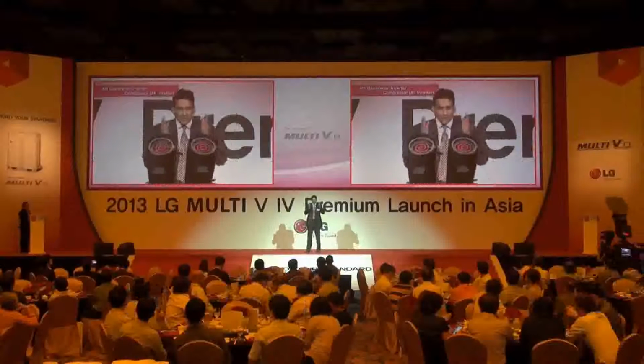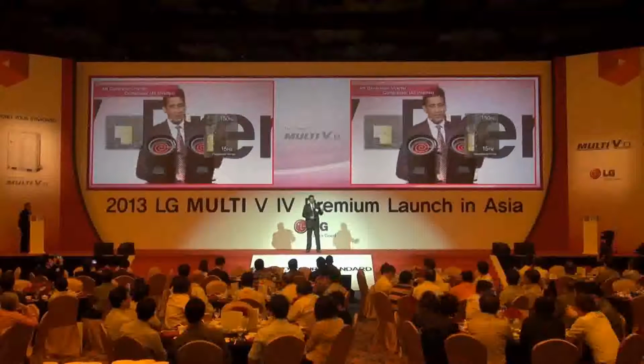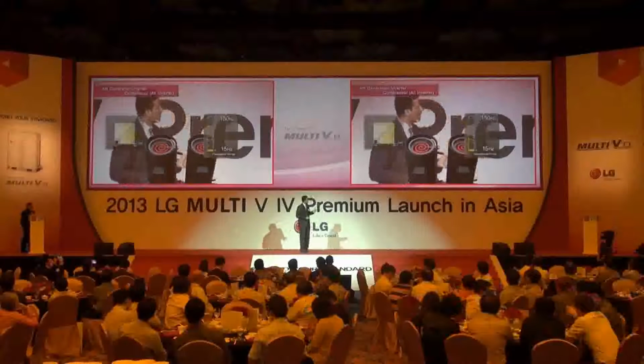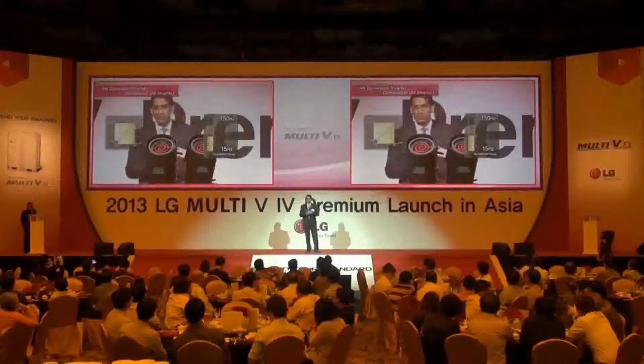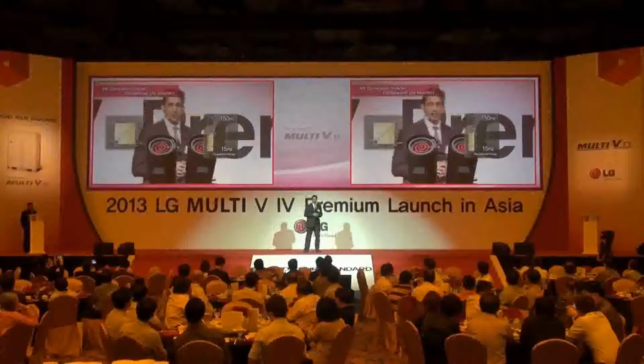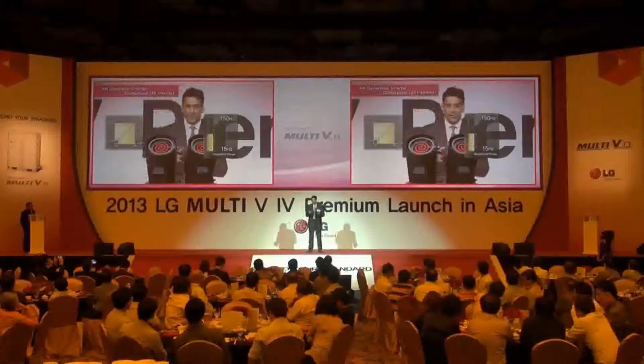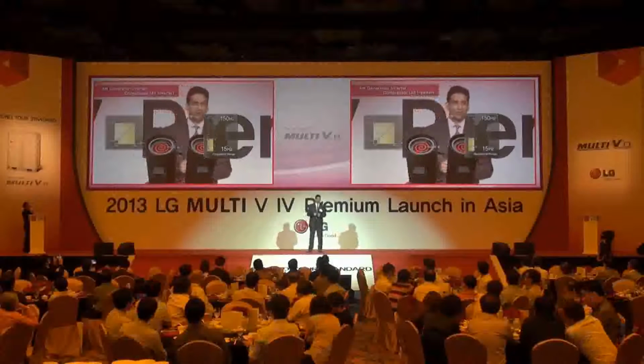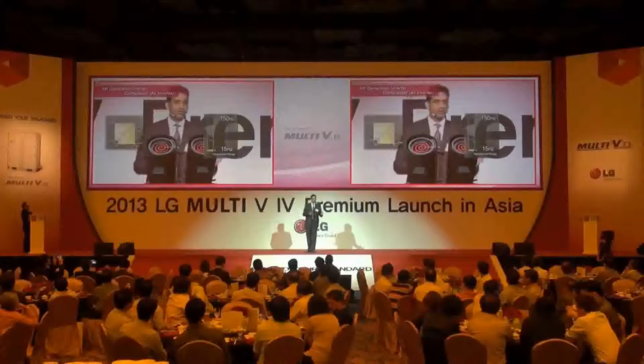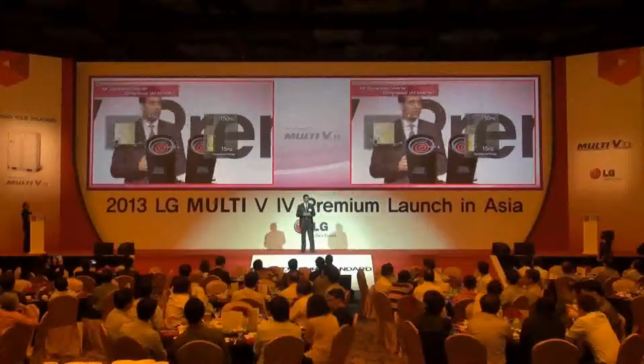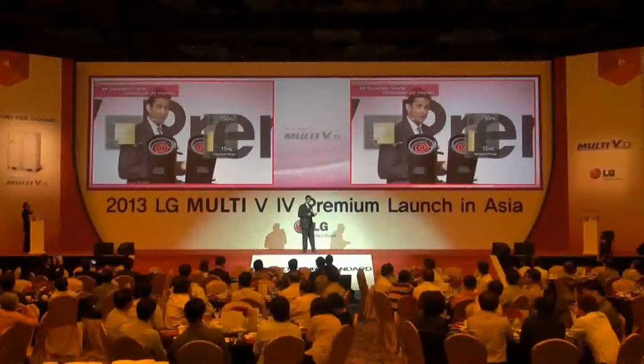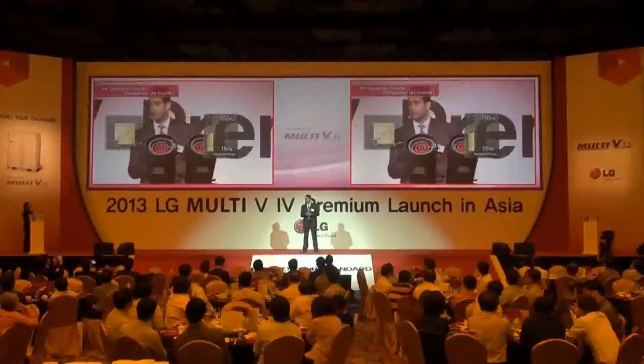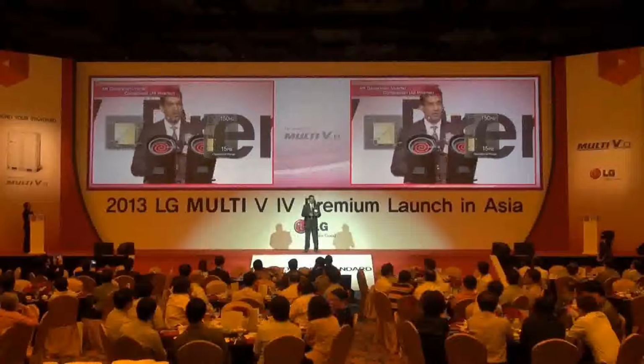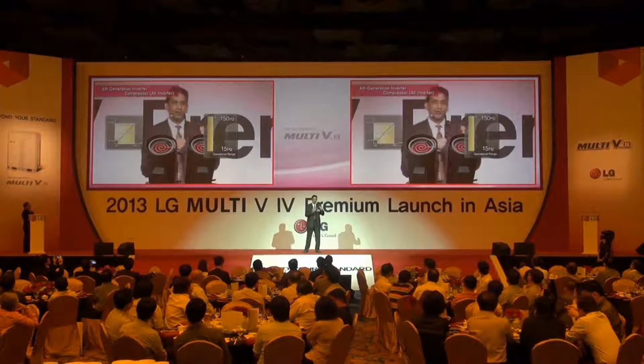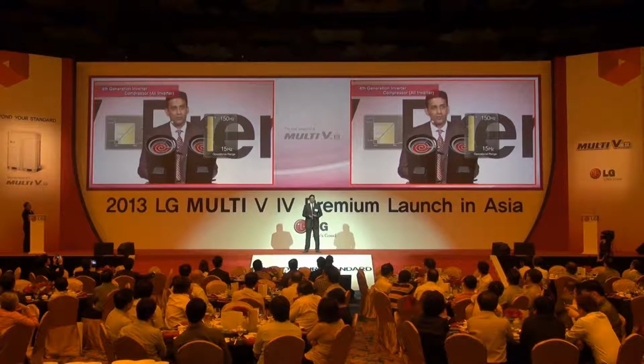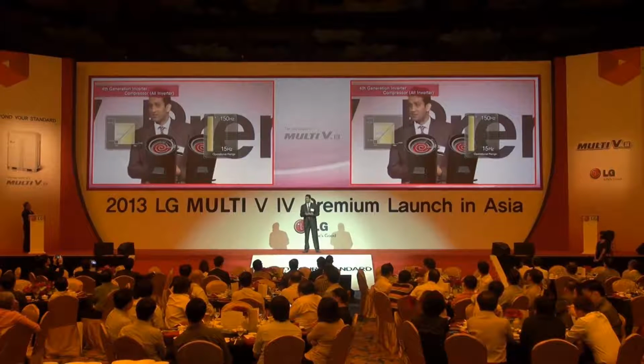Not only that, we have come up with a greatly improved operational efficiency as well. You can see over here that the operating range for MultiV 4 is now from 15 Hz to 150 Hz. I'm not so concerned about the 150 side, but I'm more impressed with 15 Hz. Why? For any one of us, we can all understand that for any VRF system, part load or low load is the real load. Very seldom do we have 100% cooling operations or 100% heating operations. So for any VRF system, to me, to R&D and to engineers, part load is the real load. And to have 15 Hz means we can go as low as 10%, 15% of running operation. This means our system can still give you the best of efficiencies at 15 Hz. Previously, our range was from 20 to 120, but we have improved upward and we have improved downwards also. Downward is not a negative term; here it means improvement in the lower part of the frequency.